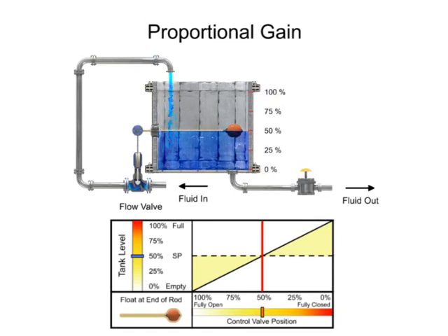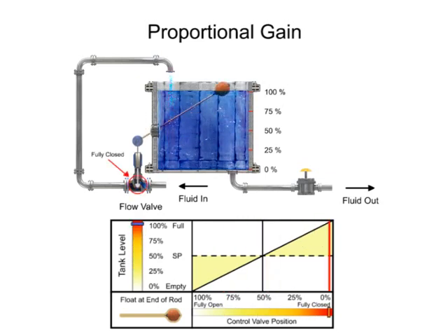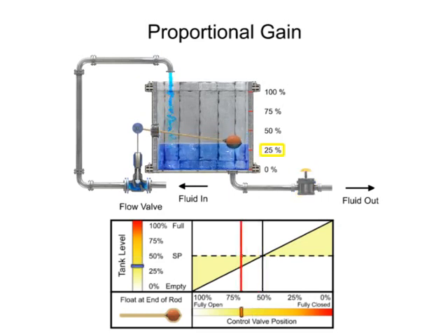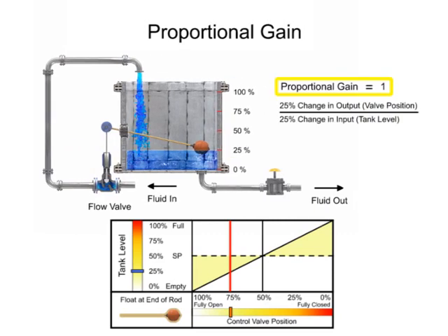The valve is actuated by the float to a fully open position when the tank level is low, and fully closed when the tank level is full. Opening the drain valve increases the load demand, which causes the tank level to drop by 25%. The float drops and the valve opens 25%, which allows more fluid flow to enter the tank. A gain of 1 is demonstrated in this mechanism, since the 25% change of input, or tank level, results in a 25% change of output, or valve position.